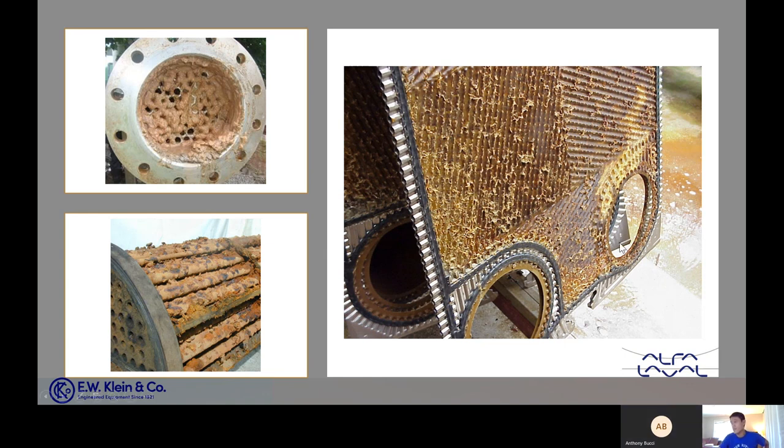And on the other side, the plate and frame, I mean, it's easier. It still gets fouled up. Like this one here gets fouled up, but it's easier to clean. It's easier to get to. You can take a brush to it or you can take just a high pressure water hose to it. And so the shell and tube, you have to soak them in chemical and it looks like you would have to ramrod a brush in there. Whereas the plate and frame looks like it disassembles easier and you can access the fouling. That's a really big advantage for a plate and frame because you can get to the surface and clean it. I mean, we still don't recommend from Alfa Laval side that we don't recommend you open up and clean it all the time. Because, like these gaskets, when you take it apart and put it back, you can damage those gaskets. When you press it together, you can press the plates. With anything like a laptop, you don't want to open it all the time. Just really, when it has a problem, then that's the last resort. When it does come to the point, it's easier to deal with a plate and frame rather than a shell and tube.